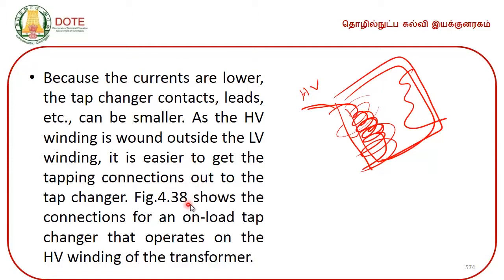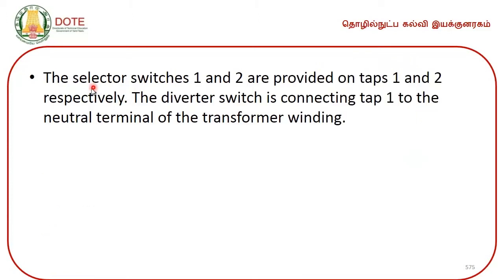Figure 4.38 shows the connections for an on load tap changer that operates on the HV winding of the transformer. Now, the selector switches 1 and 2 are provided on taps 1 and 2 respectively. The diverter switch is connecting tap 1 to the neutral terminal of the transformer winding.